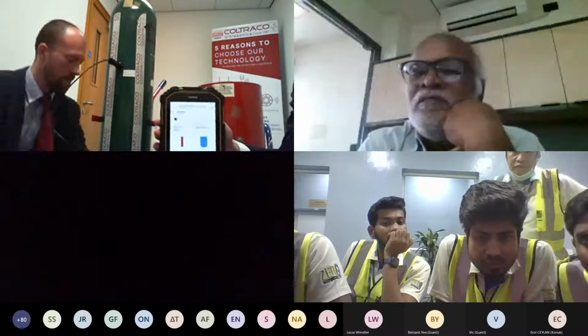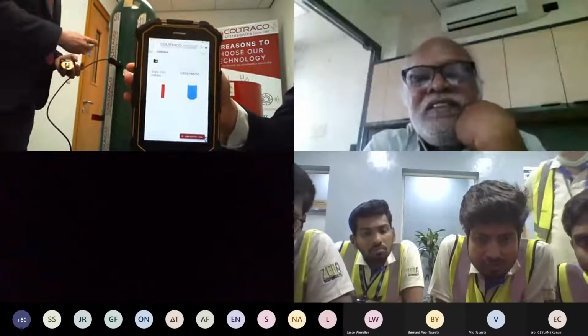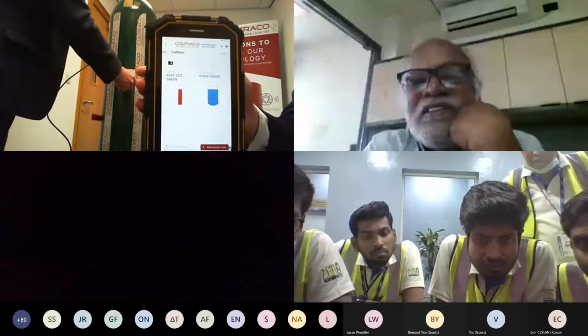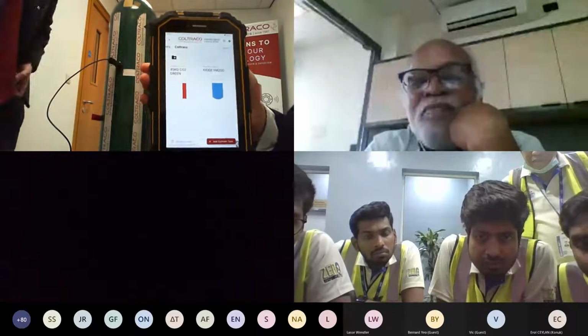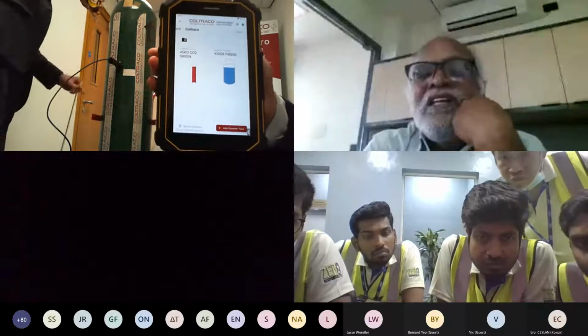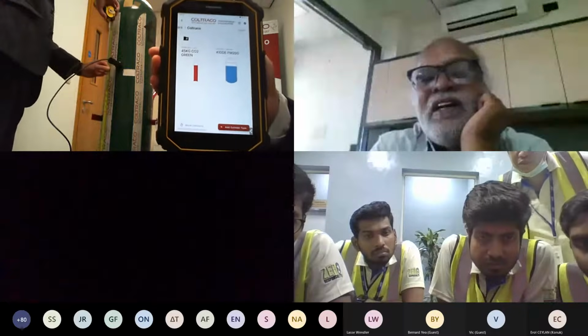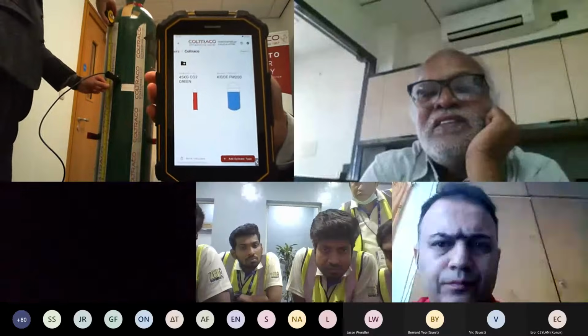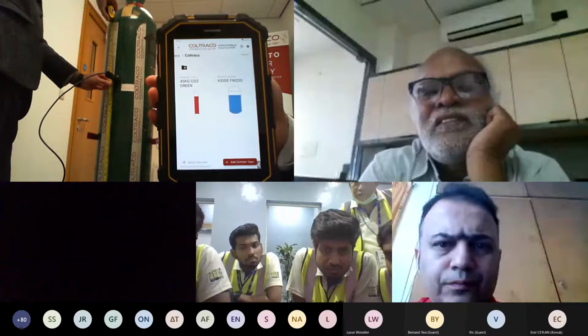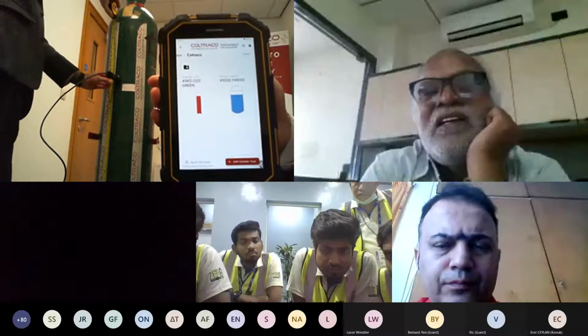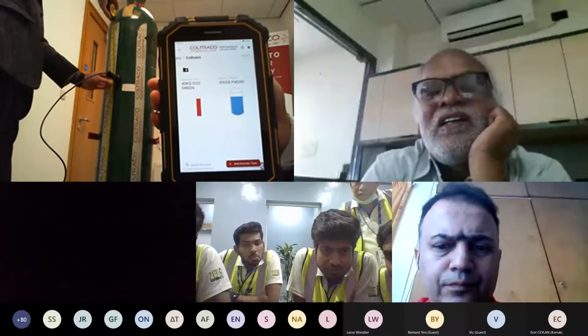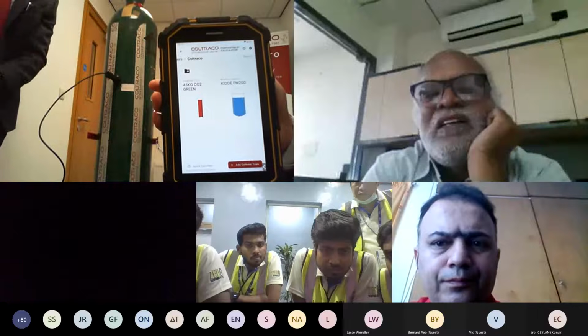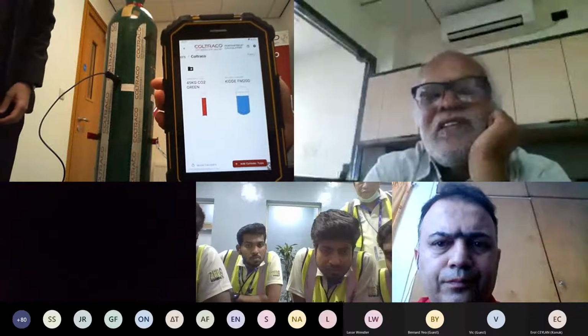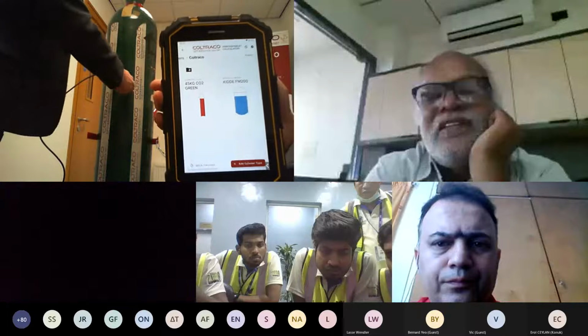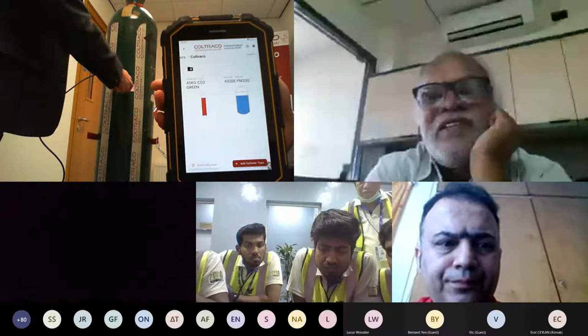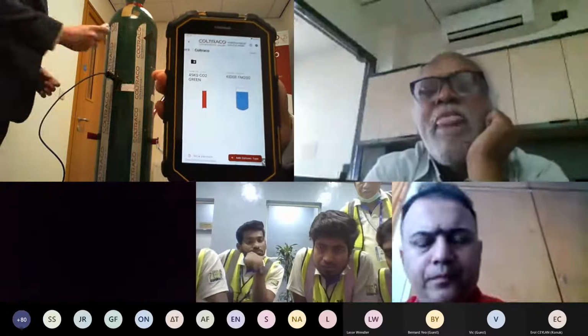So as Benjamin was doing the test for the Portalevel Max Plus, this is our Portasteel calculator. The Portasteel calculator functions to convert the liquid level height found using the Portalevel Max Plus into agent weight. The reason why we want to do this is because most fire cylinders only note the agent weight on the cylinder. They don't actually contain any information relating to the liquid level. Filling stations and cylinder manufacturers do not usually include what the actual liquid level of the cylinder should be. They only include the agent weight. Hence why we developed the Portasteel calculator to enable traceability.